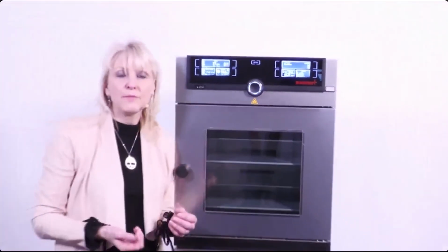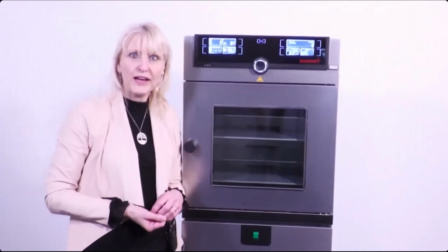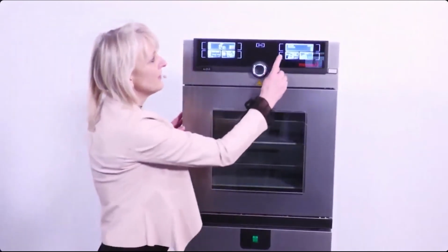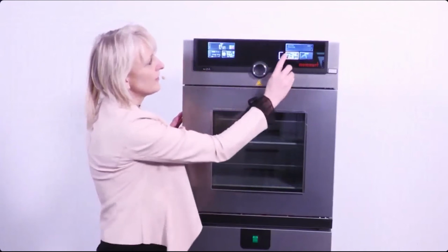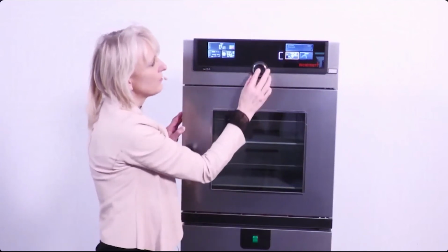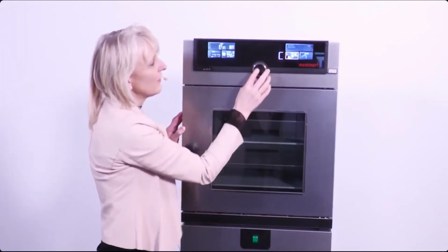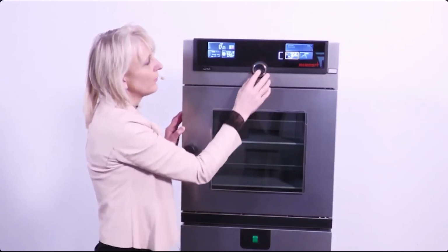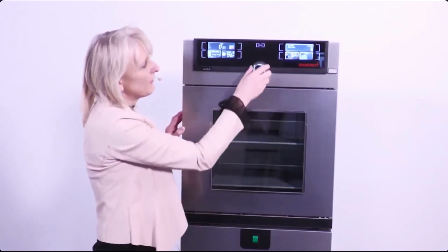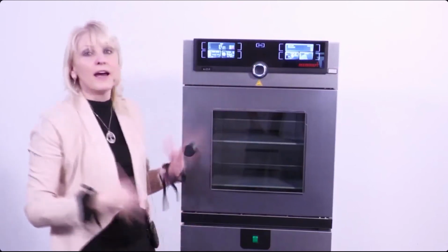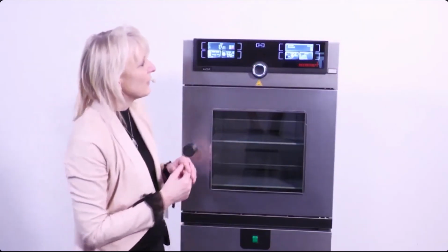We have an over temperature alarm, an under temperature alarm, and the same also for pressure. When you go here, you can see temperature settings, and here we have pressure where we can set maximum and minimum pressure alarms for our vacuum ovens.